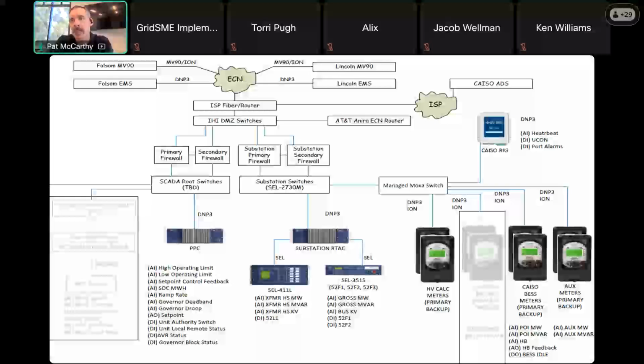As Kelsey mentioned, you're going to want somebody from your substation team there on site, or at least remote but able to access devices locally on site. By devices, I mean those relays and the substation RTAC, anything providing that kind of substation data into the rig. And again, CAISO requires that the originating device send the data through intermediate devices, like a substation RTAC, up to the rig.